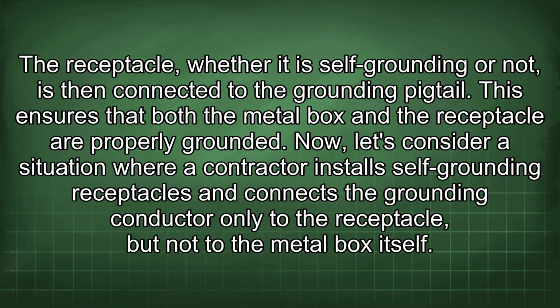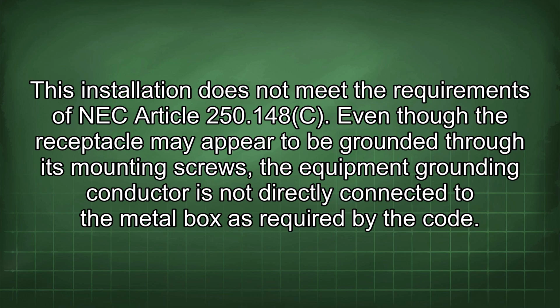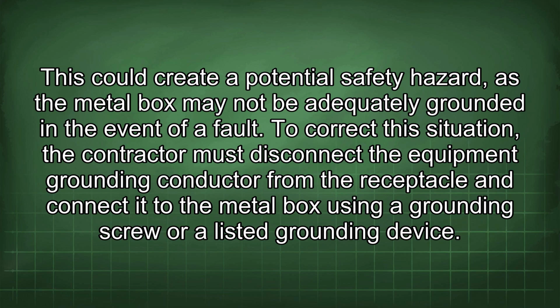Now, let's consider a situation where a contractor installs self-grounding receptacles and connects the grounding conductor only to the receptacle, but not to the metal box itself. This installation does not meet the requirements of NEC Article 250.148C. Even though the receptacle may appear to be grounded through its mounting screws, the equipment grounding conductor is not directly connected to the metal box as required by the code. This could create a potential safety hazard, as the metal box may not be adequately grounded in the event of a fault.